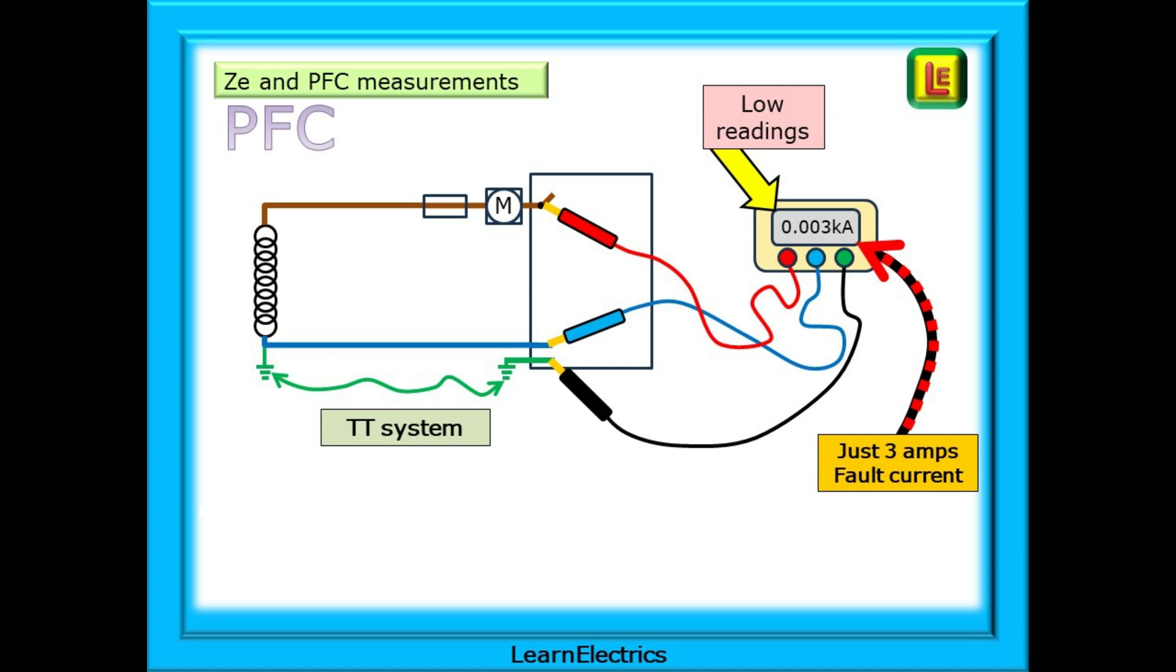This time the reading is 0.003 kiloamps. Your assessor may well ask you to convert this reading of 0.003 kiloamps into amps and to comment on it. This is just 3 amps and can be explained because it is a TT system with a high ZE reading. The ZE is going to be 240 volts divided by 3 amps or about 80 ohms of resistance and this is about right for a TT system.